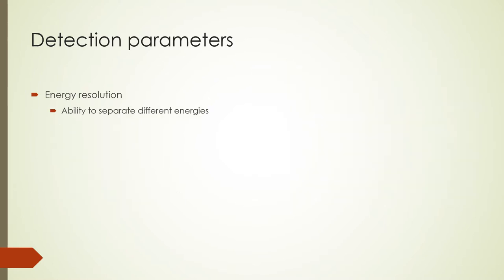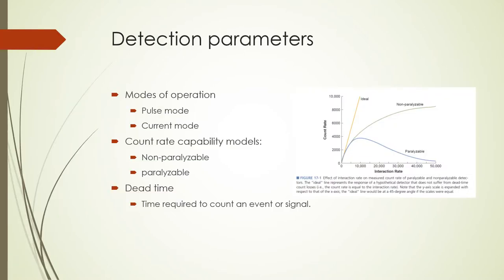Energy resolution is the ability to separate different energies from each other. When counting radionuclide decays, the photon or particle radiations from different radionuclides can have different energies. The ability to detect these energies and display them is what a spectrometer does. Detectors may be operated in pulse mode or current mode. In pulse mode, each signal is treated individually, while in current mode, signals are averaged and treated as a current. Dead time is the time required to count an event or signal. During the dead time, other pulses are not counted.